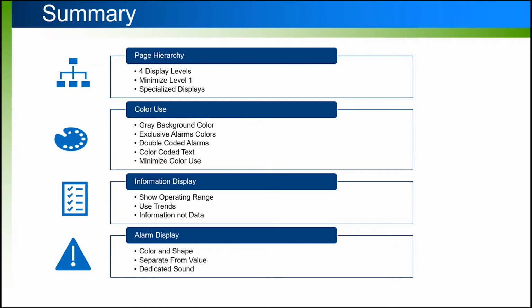When we talked about information display, we showed the operating range for the data that's being shown, not just showing the data. The data is good, but show me where that data point is supposed to be. Use trends where possible, so you can tell where the process is and where the process is going. That's the kind of situational awareness you can provide with the screens, which helps an operator quickly identify what the problems are and get down to the root cause, because we want to show information, not just data.